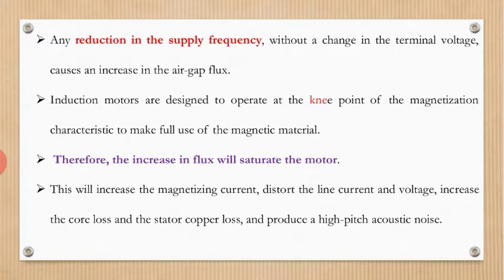Therefore the increase in flux will saturate the motor. This will increase the magnetizing current, distort the line current and voltage, increase the core loss and stator copper loss, and produce a high pitch acoustic noise.